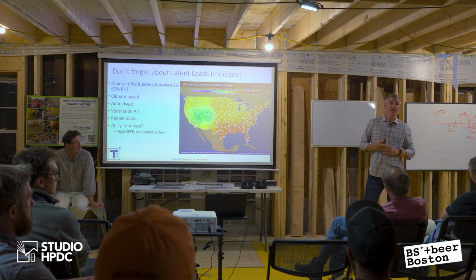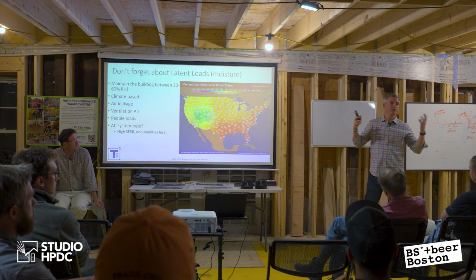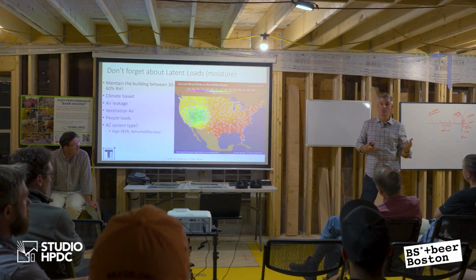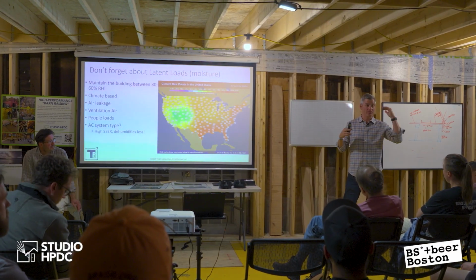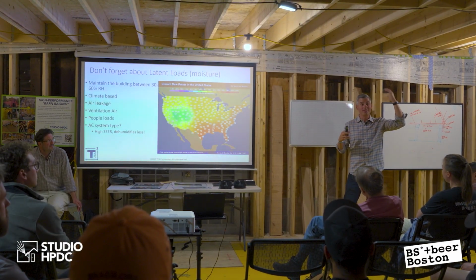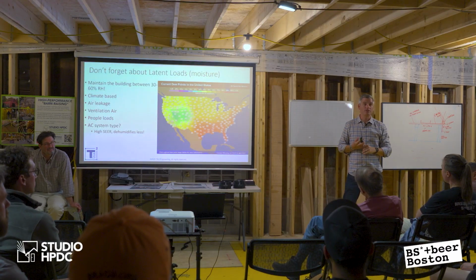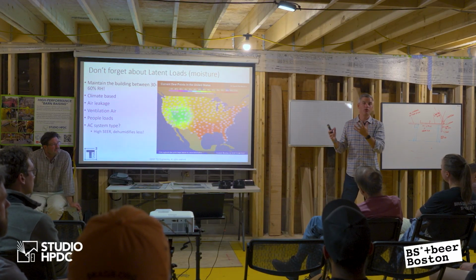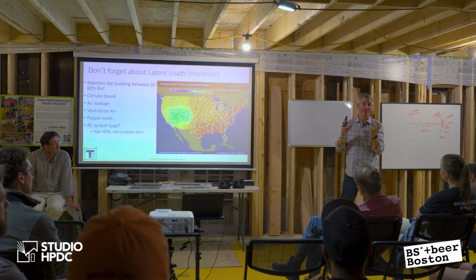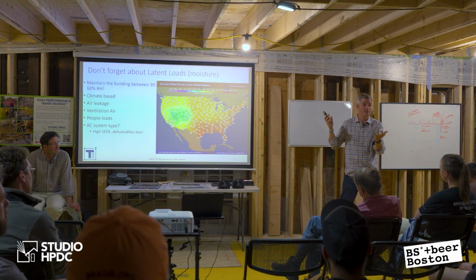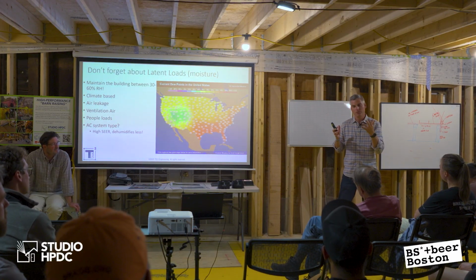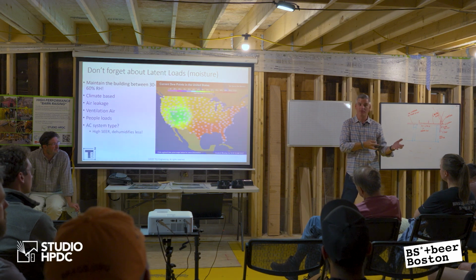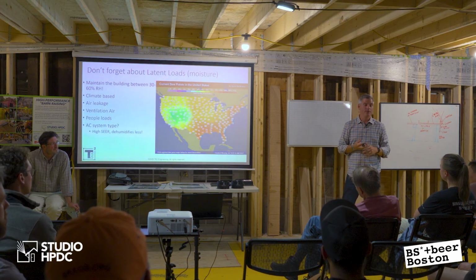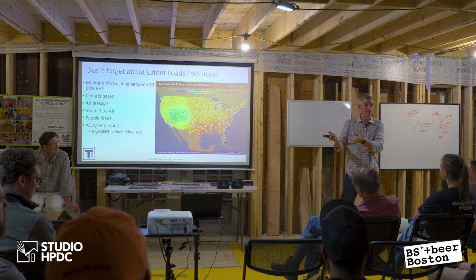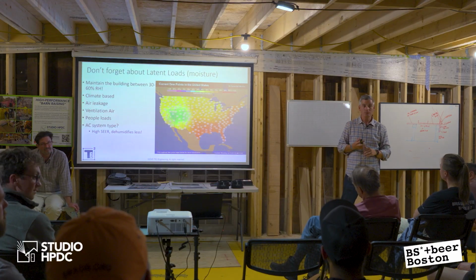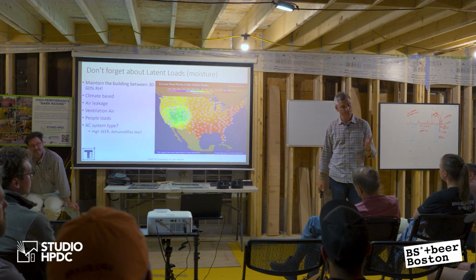Well, mold is just a microcosm of not providing enough dehumidification. Mini splits, like we were talking about before, have such high sensible heat ratios, they don't do a good job dehumidifying. That's the problem. Mini splits are getting misapplied, and the technology is going to higher sensible heat ratios because that's how the rebates are incentivized. So you're going to have to put in ducted dehumidification with that style of unit. There's no way that I know how to make that system work with a traditional mini split. The system you were talking about doesn't have that problem. Exactly.